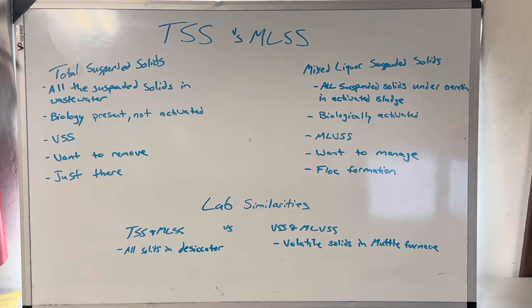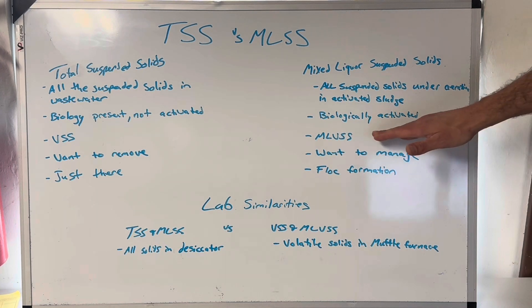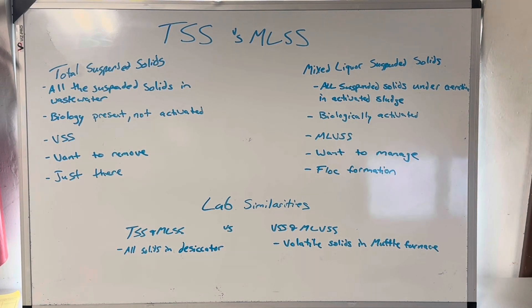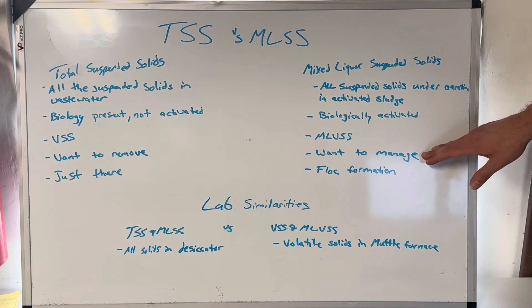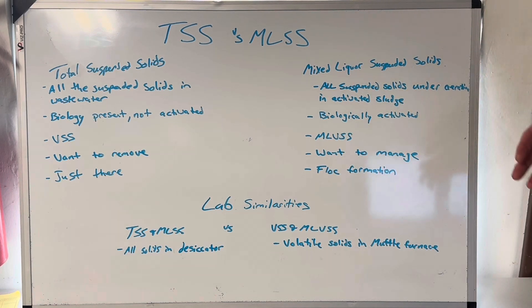The MLSS is all the solids; the MLVSS is the percentage that is volatile, and you're typically going to see over 75% is good. I actually run around 90% volatile — it goes through several phases before it gets to my aeration basin so I don't have a lot of inert stuff floating around. When I get to the preliminary treatment video, I'll tell you about an activated sludge plant where you can see all sorts of stuff floating around because it had no preliminary treatment. You want to manage MLSS — you're not trying to get rid of it. You will have target wasting rates where you are wasting a certain amount of MLSS to a digester or thickener to keep the amount you want.